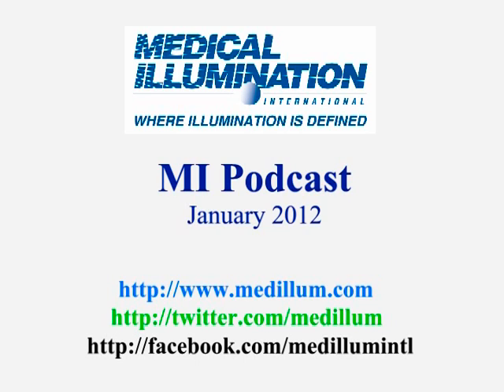And again, like I mentioned, on either the minor procedure or minor surgery procedure lights like the MI 1000, the MI 500, the Centurion on that line, I would say that probably to remove and replace a single light's probably about an hour. Two lights, like a dual unit, would be about an hour and a half.